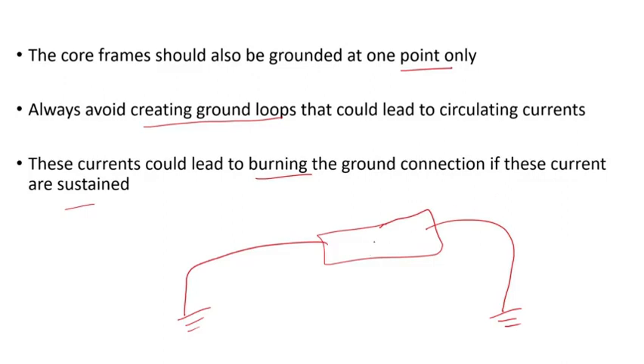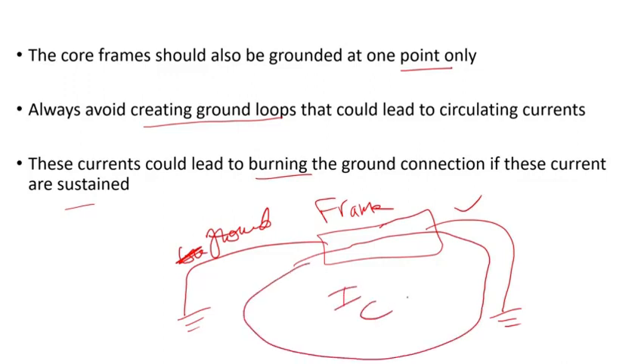But the problem is, again, this is just a hypothetical example, just to give you an idea. So you have the ground, the jumper, and there's another one here. Now, because you have leakage flux, which is going to induce eddy currents and other things, current can flow from here to the ground and back. So you're going to have some circulating current. If it's sustained for a long duration, and it depends on its magnitude, it could overheat this jumper and ultimately cause it to melt. Now you've lost that ground, and it could do the same thing here. Now you've lost that ground, or it could cause overheating of the frame. So it can cause all kinds of other things. It's always better to just have one ground, so that way you avoid creating a loop.